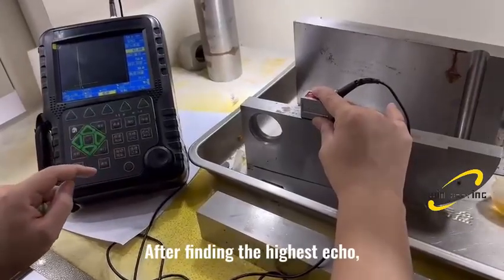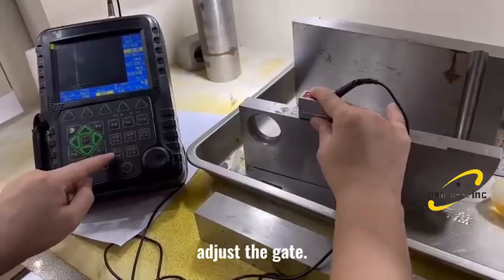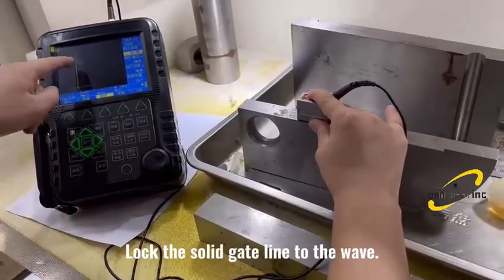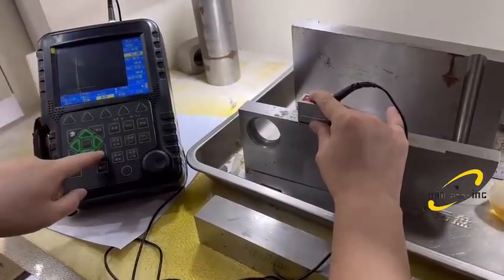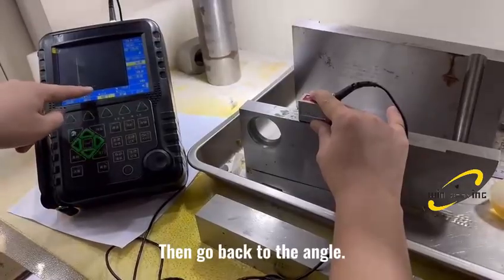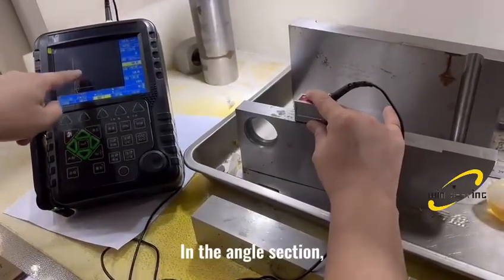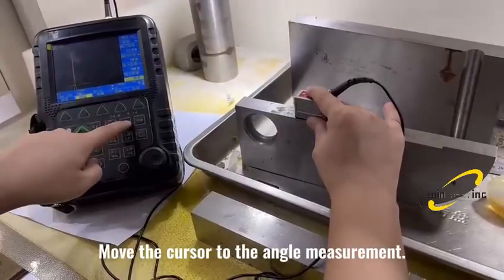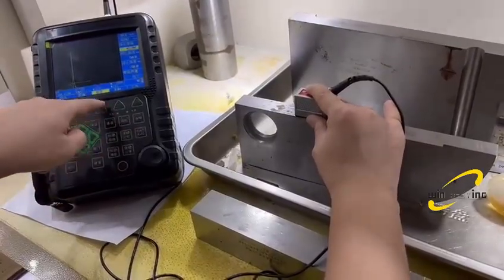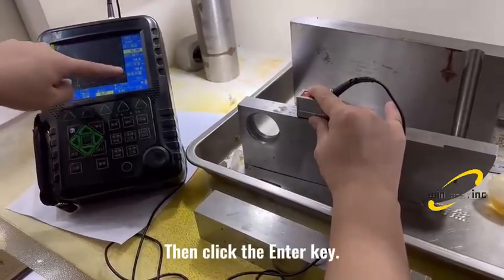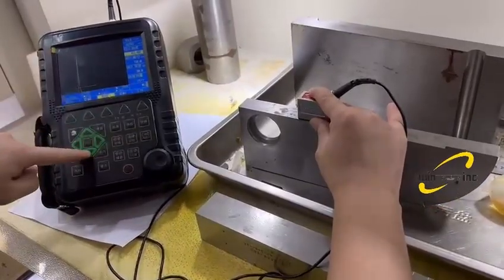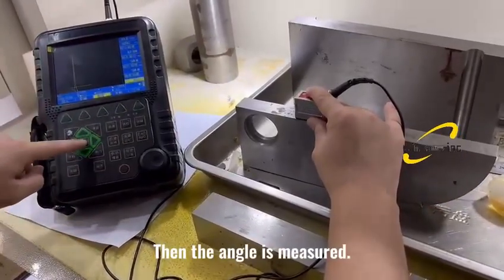After finding the highest echo, adjust the gate. Lock the solid gate line to the wave. Then go back to the angle. In the angle section, move the cursor to the angle measurement. Then click the enter key. Calibration completed. Then the angle is measured.